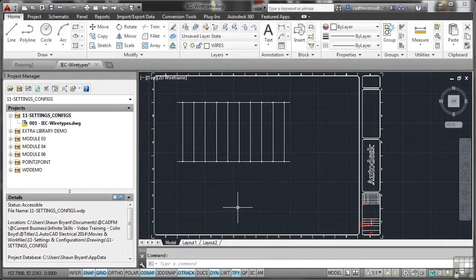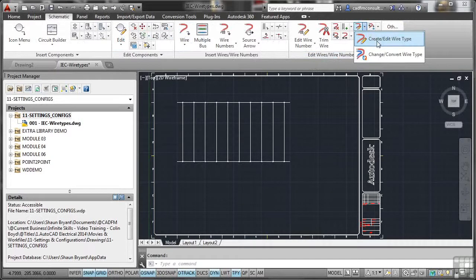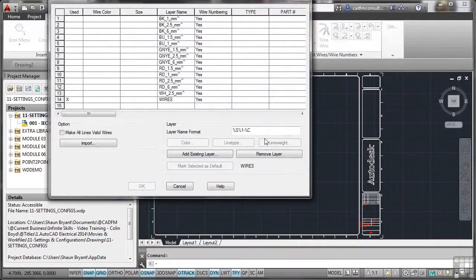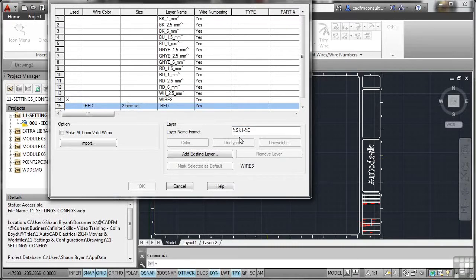I'll OK that and OK the dialog box — those settings have been set in the project. Now go to the schematic tab, go to edit wires and wire numbers, and in that panel click the fly-out and select 'Create, Edit Wire Type.' This brings up a large dialog box where we're going to create new type number 15. You'll see there are already some existing layer names. I'm going to work with a new layer. Wire colour I'm making red, size 2.5 millimetres with SQ — you'll see why in a moment. %C stands for colour and %S stands for size.